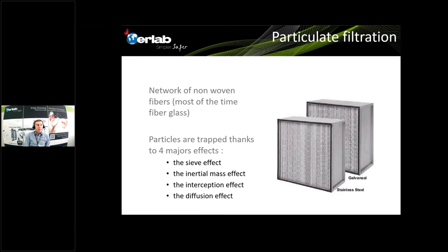Particulate filtration is most of the time performed with HEPA filters. Many people have been educated about HEPA and ULPA filter definitions thanks to the COVID-19 crisis, because this technology is one of the only ones available on the market to efficiently trap viruses and bacteria. It is made of a network of non-woven fibers, most of the time fiberglass, but also polymeric materials. This network of fibers can trap particles thanks to different effects: the sieve effect, the inertial mass effect, the interception effect, and the diffusion effect.